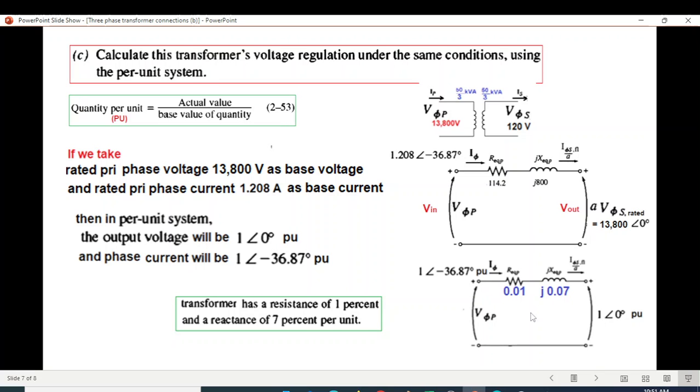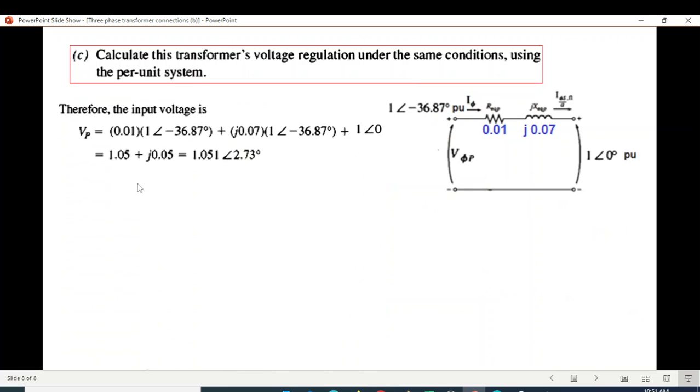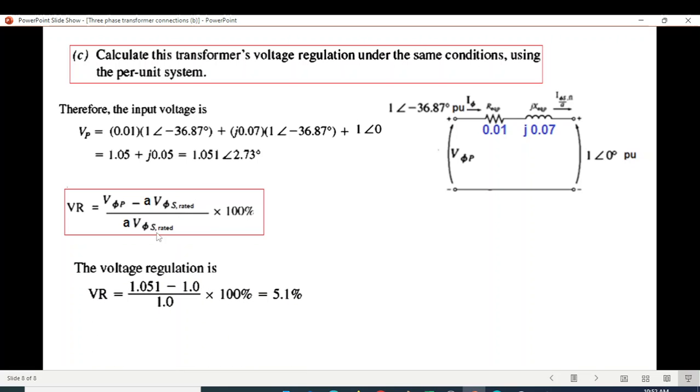Again by writing KVL, V phase P. So V phase P: current multiplied by resistance, reactance multiplied by current, plus this voltage. We get VP: 1.051 angle 2.73 in pu. Now voltage regulation formula, same formula. We use the value in pu. V phase P is 1.051. So where it is, we write 1.05. Where A V is, we write magnitude 1 divided by 1. So here we get the answer: 5.1%, exactly the same answer that we calculated in part B.